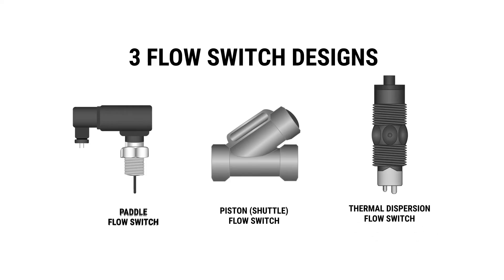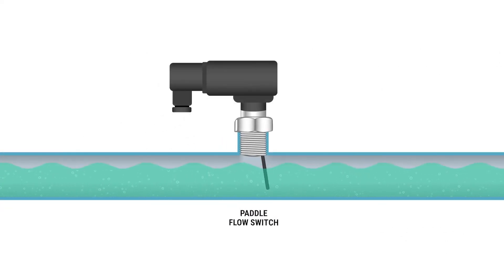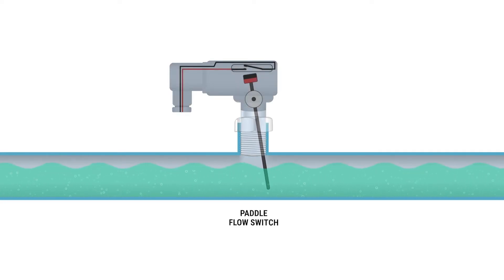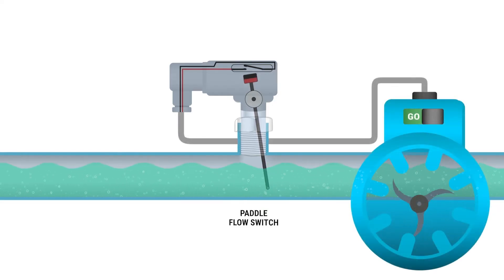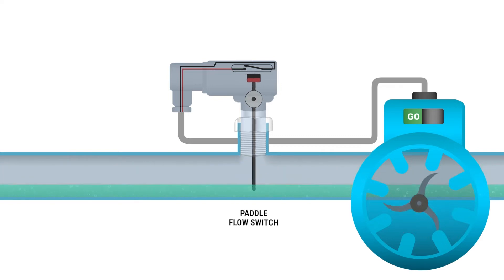First, let's look at a paddle type flow switch. The paddle design flow switch has a hinged or spring-mounted paddle making direct contact with the media flowing through the pipe. Media flowing at the target rate or set point holds the paddle in position. An increase or decrease in the flow rate moves the paddle, which throws a small switch, triggering the specified action.